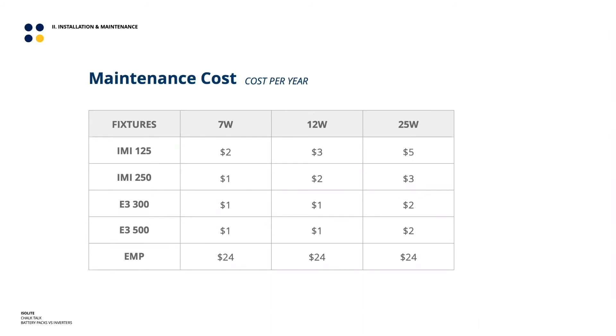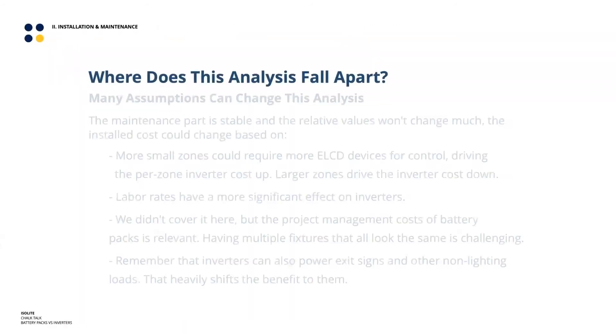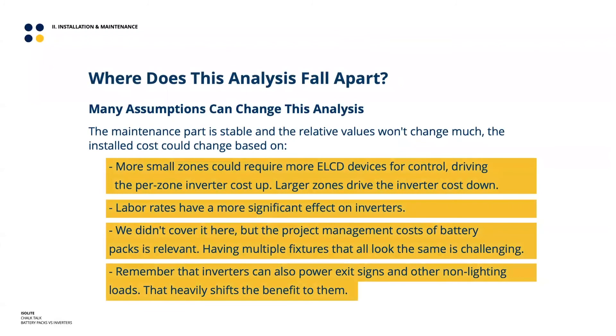Because you can fit so much more capacity on an inverter, the maintenance cost per fixture per year goes way down. On a fixture-by-fixture basis, fixtures on an IMI can cost just $2–$5 per year to maintain depending on wattage and quantity. By contrast, the cost per year for a fixture with battery backup is about $24, and that doesn't really change based on wattage since you're always running back and forth between all those individual devices.